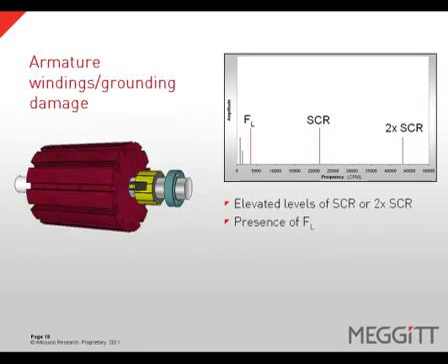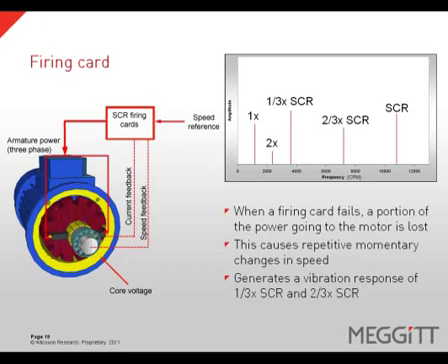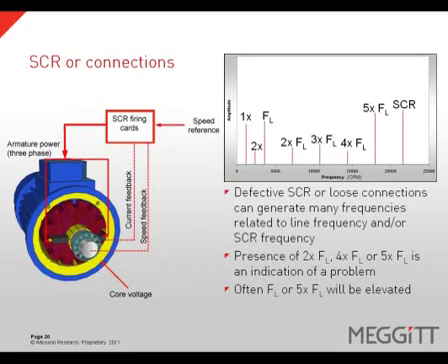Damaged or grounded armature windings will show elevated levels of SCR frequency or two-times SCR frequency, and you will likely see a peak at one-times line frequency. When an SCR firing card fails, a portion of the power going to the motor is lost, causing a momentary change in speed that generates vibration at one-third SCR frequency and two-thirds SCR frequency. A defective SCR or loose connections can generate many frequencies related to line frequency and SCR frequencies. The sheer presence of two-times, four-times, or five-times line frequency is an indication of a problem, and often one-times or five-times line frequency will be elevated.